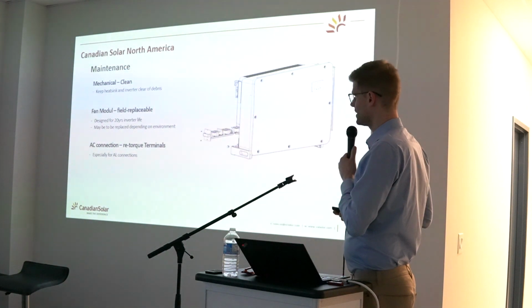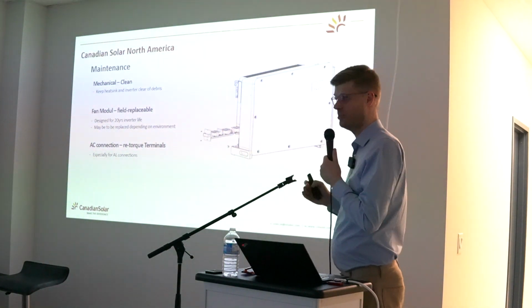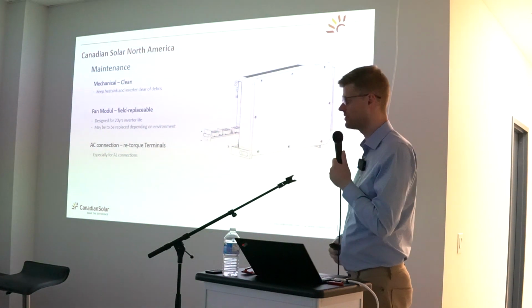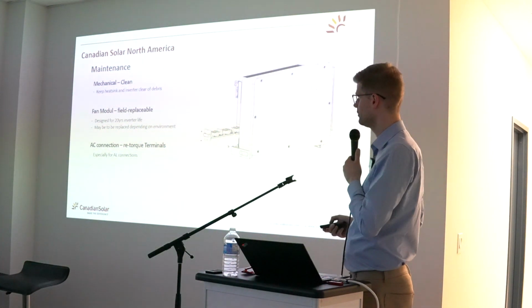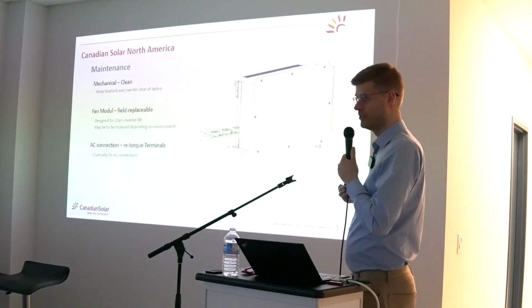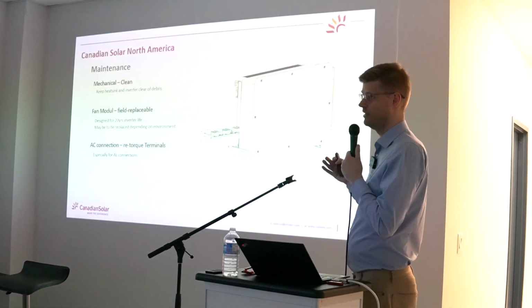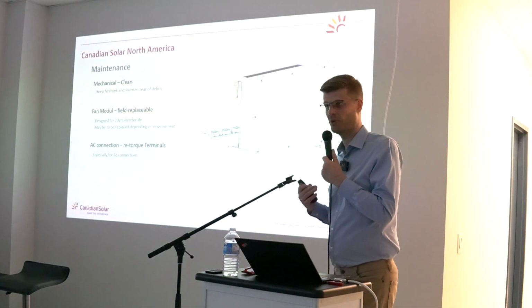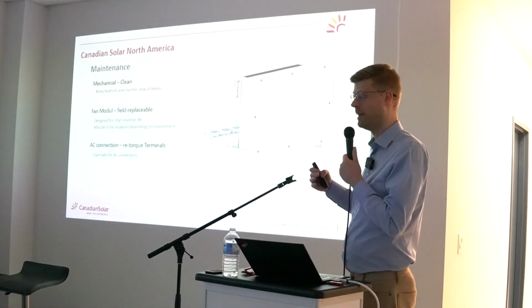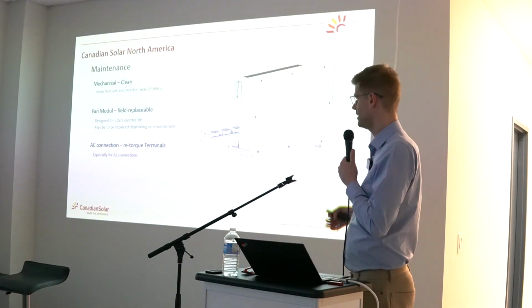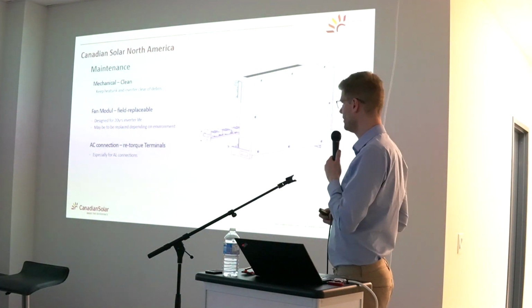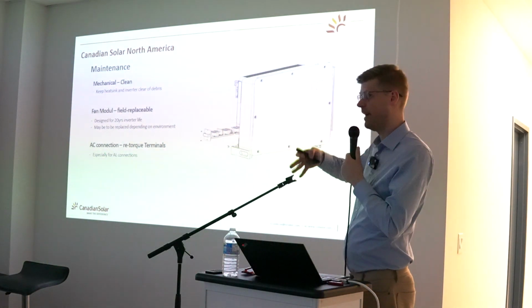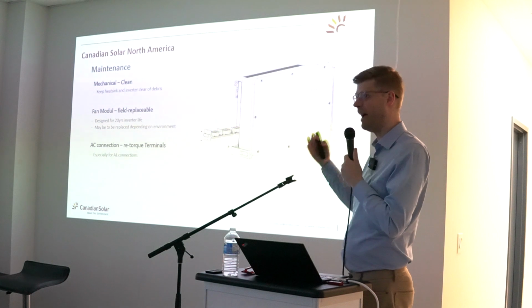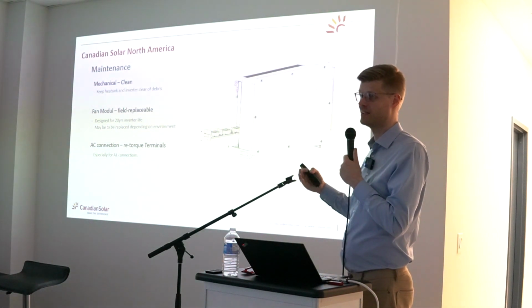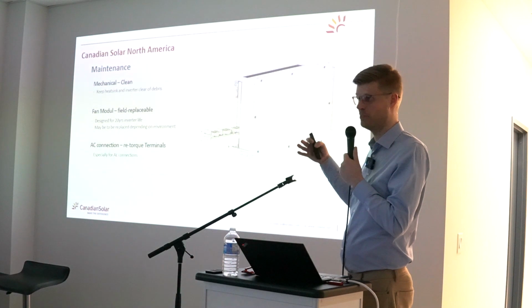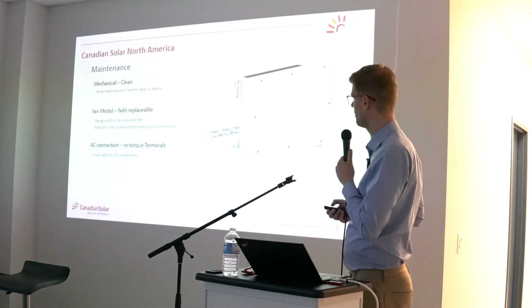On the maintenance side of things, string inverters are very, very simple compared to more conventional central inverters in that larger power frame. They're completely fan-cooled. That's the first part. At that power level, passive cooling is not really possible anymore because you have an extremely high power density based on the size of the unit as well as on the weight of the unit, of course. So power versus weight, power versus volume. And these units still have a heatsink in the back, but a fan that is assisting as soon as the heatsink cannot dissipate the heat on its own by just rising of the hot air through the heatsink on top.